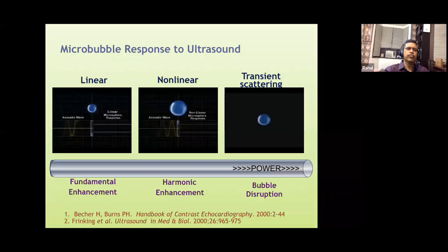So this is what happens. The signal obtained from the ultrasound is transmitted. The machine, we have settings available on most vendors, as I mentioned. We can choose the preset setting of LV opacification, which will automatically shift us to lower ultrasound energy. Besides, we also can manually adjust the mechanical index, which is also available with most vendors.